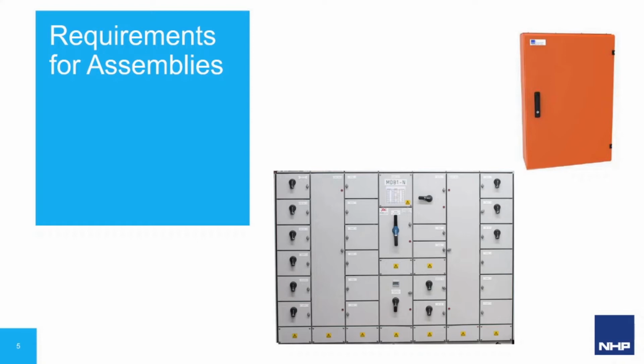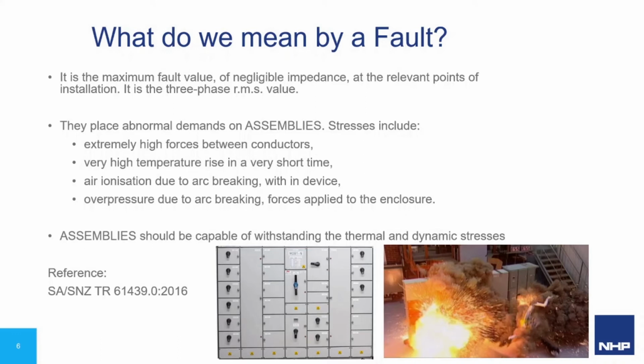So now we will have a look at some of the definitions which broadly define a fault and have a look at the requirements of our assemblies under these conditions. A short circuit is a fault causing current significantly in excess of the continuous rating of the circuit. The fault could occur downstream, external to the assembly, on a circuit that our assembly is supplying, or the fault could occur inside the assembly. The risk of an internal fault is usually reduced with an appropriate form rating. If this fault current exceeds the withstand rating of the board in magnitude or time, it will have adverse effects on the board. When rating a board for fault withstand, we are mainly concerned about the maximum faults that can occur. This is the three-phase bolted short circuit fault.